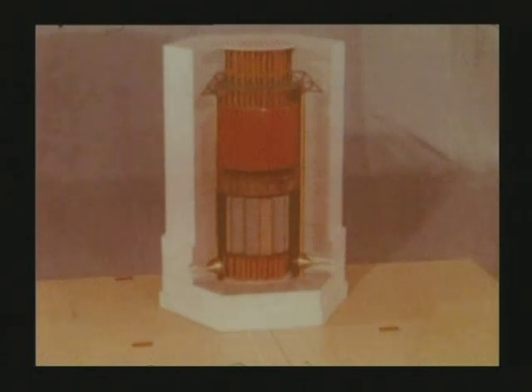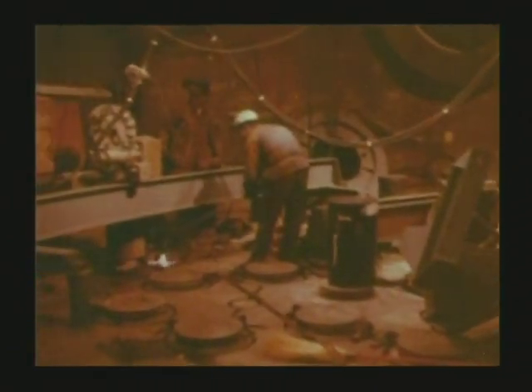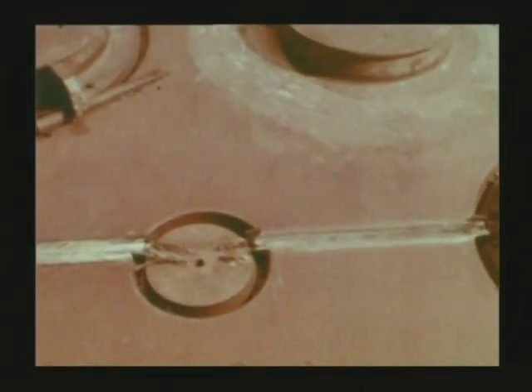The reactor vessel is made of pre-stressed concrete. It contains both the reactor and the heat exchangers. The exchanger supply tubes emerge from the bottom of the vessel. Each tube is welded to the leak-proof shell by means of automatic machines. Next, the welds are carefully trimmed and ground prior to being tested by ultrasonic devices.